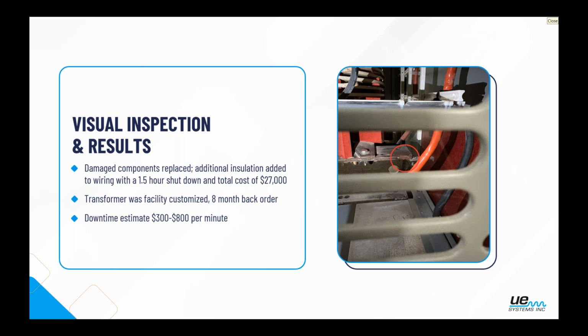Now, granted, in this example, it was a pretty severe issue. We actually had one of the wires rubbing on the bus bar, and it had occurred for so long that it was starting to weld itself, basically. And this would have been a catastrophic failure.